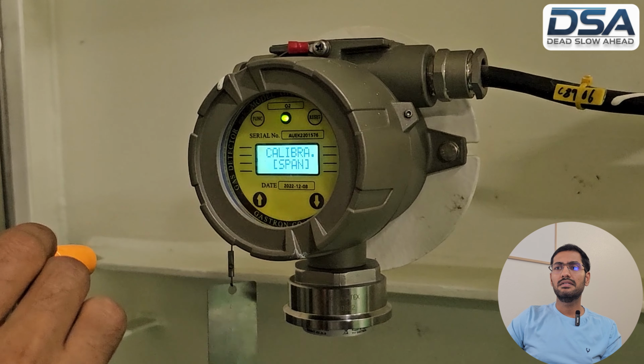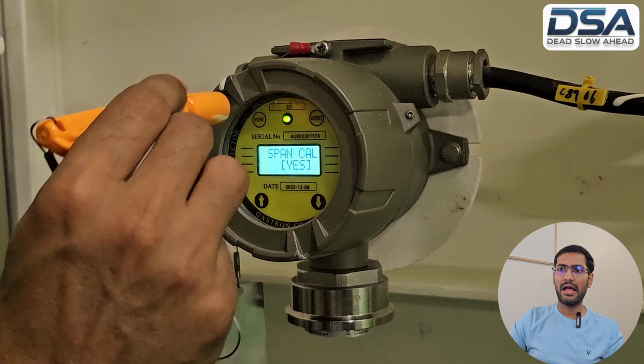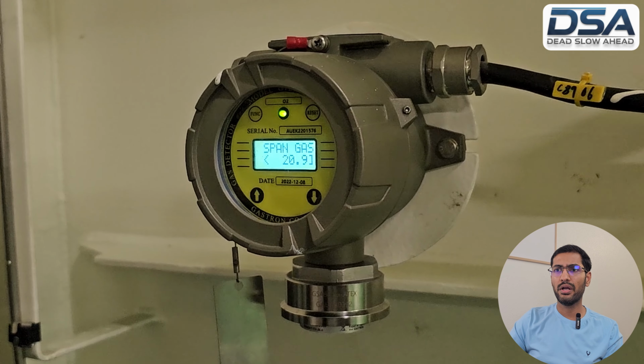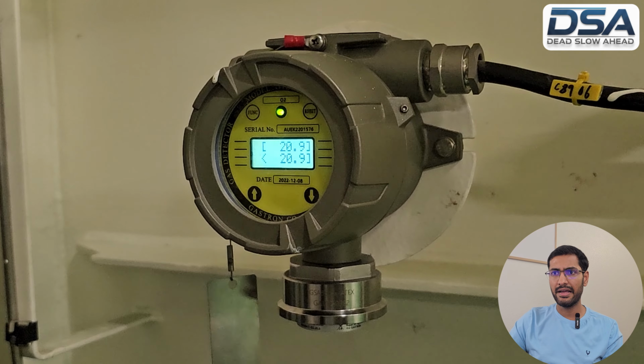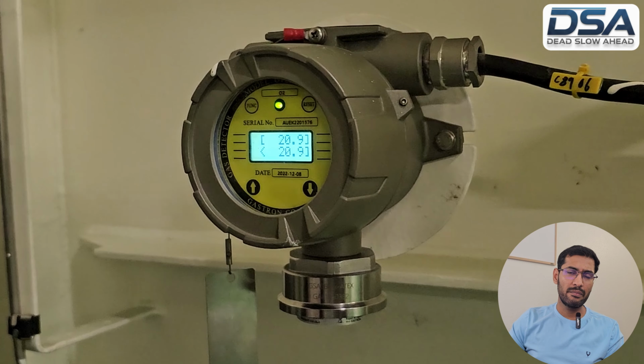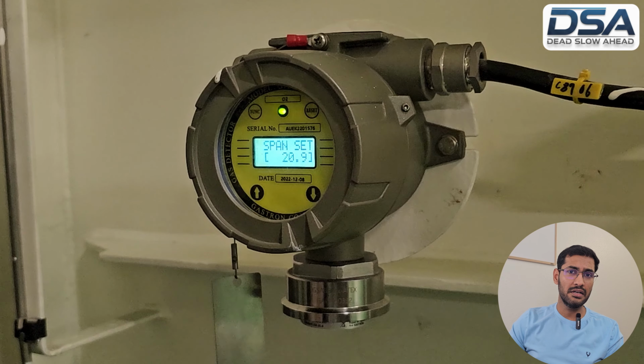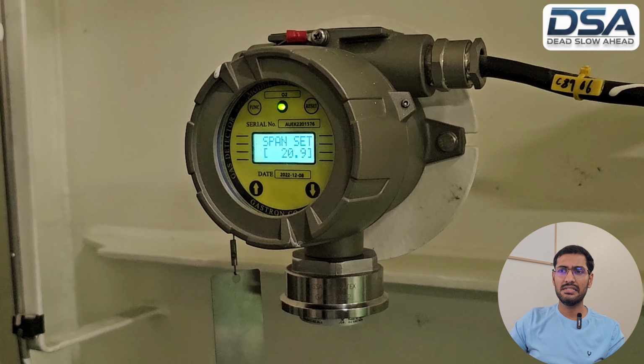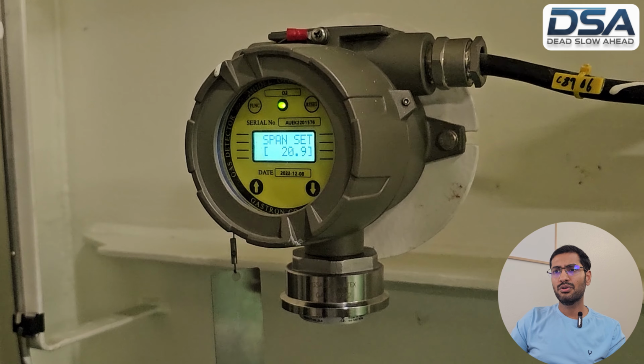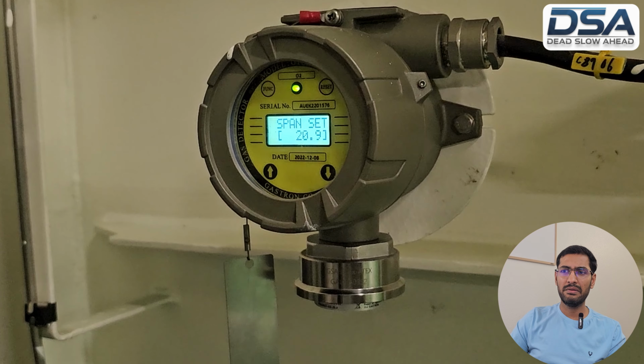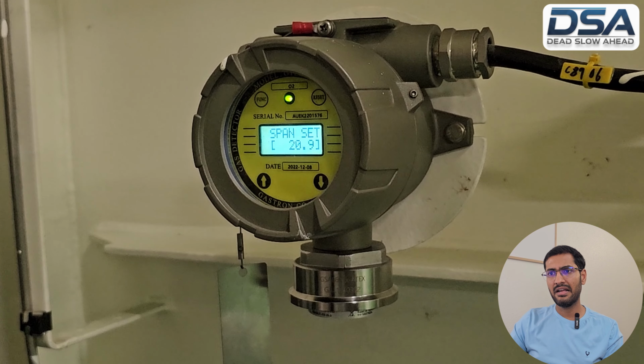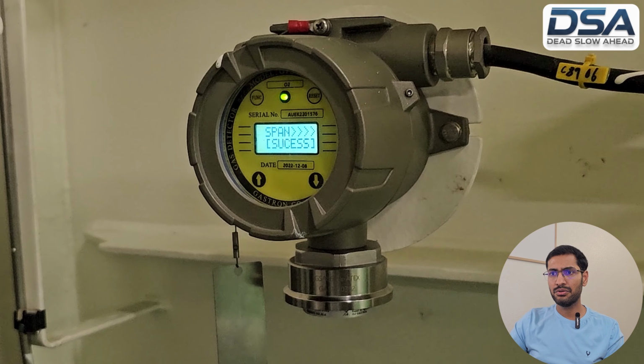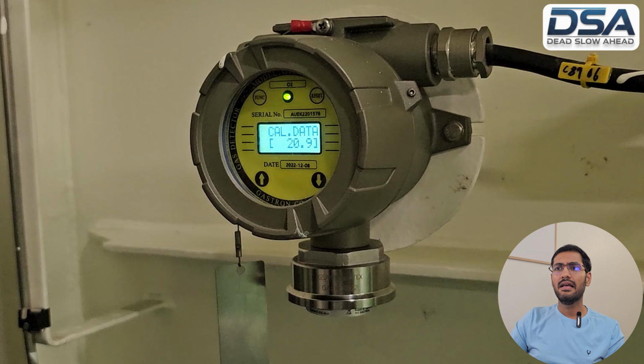Next is the span calibration. As we discussed earlier, we need to expose the sensor to normal atmospheric air, where the oxygen reading is 20.9%. So it should ideally read and stabilize at 20.9%, and after confirmation it should display success. This is how you can perform both zero and span calibration, get rid of the situation, and put the system back under normal running condition.